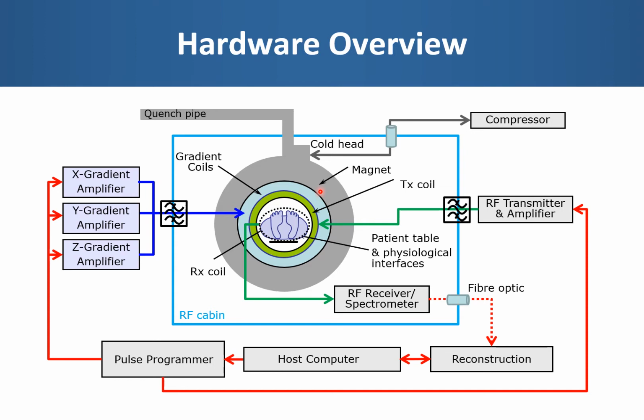Inside the room temperature bore of the magnet, we have the gradient coils connected to high power amplifiers for the X, Y and Z gradients, and they have appropriately filtered electrical connections through this RF cabin, which we'll talk about in a moment. Inside the gradient coil, we have the whole body transmit coil, typically of a birdcage design, and although it can also be used for signal reception, it is mainly used to create a relatively homogeneous transmit field inside the magnet. The transmit coil is connected to the RF transmitter and amplifier, again through filtered connections in the radio frequency cabin.